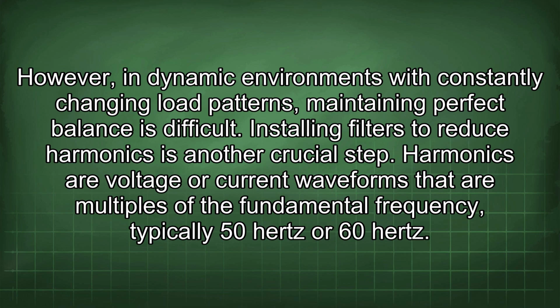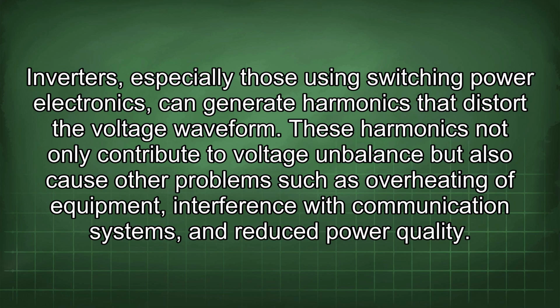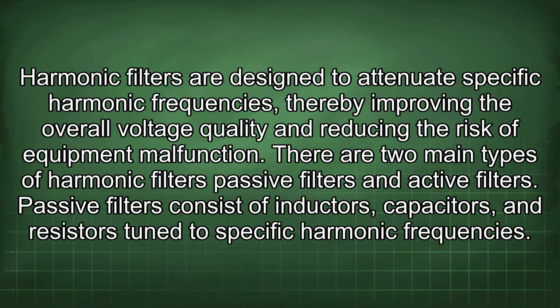Harmonics are voltage or current waveforms that are multiples of the fundamental frequency, typically 50 Hz or 60 Hz. Inverters, especially those using switching power electronics, can generate harmonics that distort the voltage waveform. These harmonics not only contribute to voltage imbalance but also cause other problems such as overheating of equipment, interference with communication systems, and reduced power quality. Harmonic filters are designed to attenuate specific harmonic frequencies, thereby improving the overall voltage quality and reducing the risk of equipment malfunction. There are two main types of harmonic filters: passive filters and active filters.